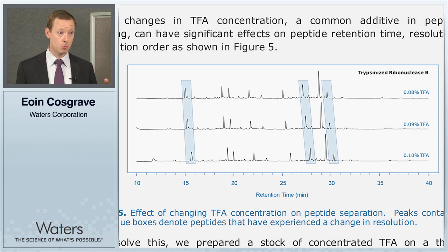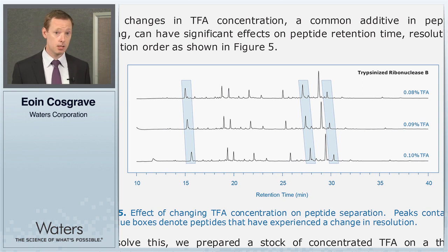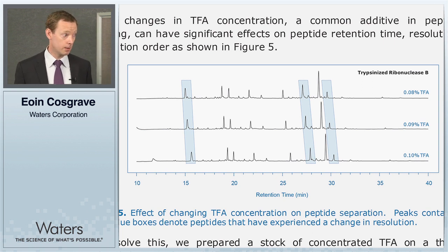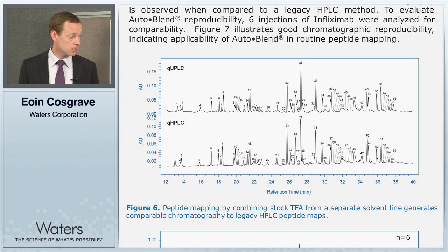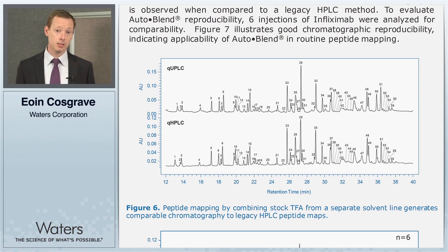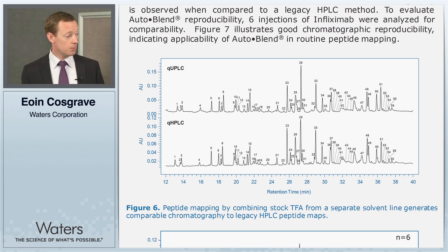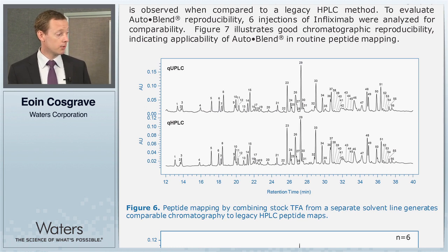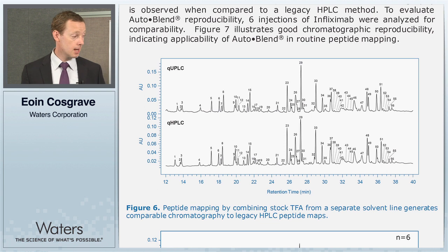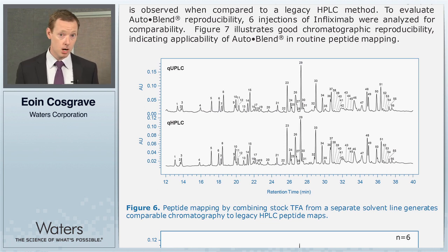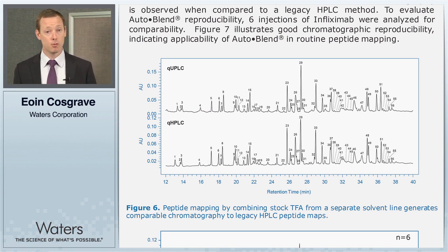When you add acidic modifiers to your mobile phases, tiny adjustments can influence the final concentration. To remove that variability, we include TFA on a third solvent line. When we do this, the results shown in figure six use a tryptic digest of infliximab, a commercially available monoclonal antibody, tracking 55 different peaks. Using AutoBlend to deliver TFA as a third solvent line, we find near-identical chromatography when comparing to the legacy HPLC instrument, with great agreement in relative retention times between the legacy instrument and the H-class Bio delivering TFA via AutoBlend.